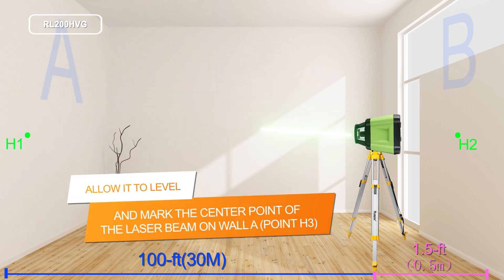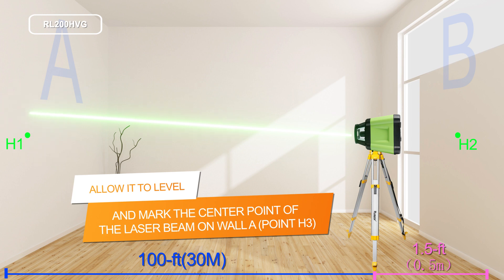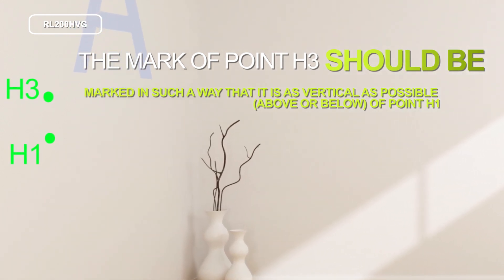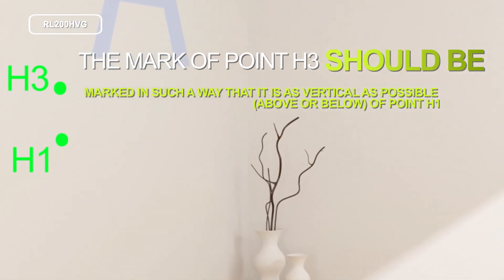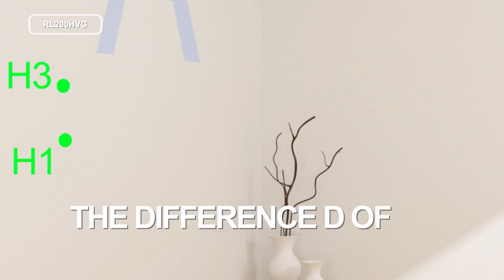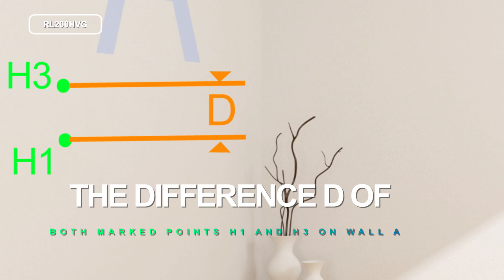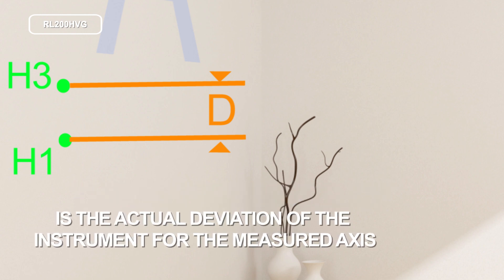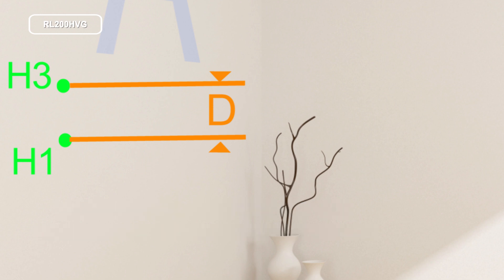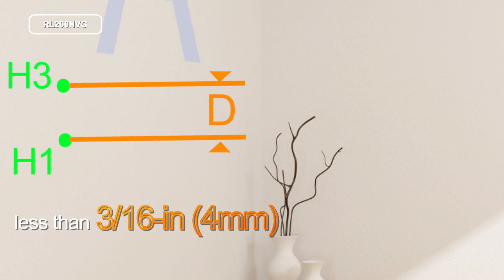Allow it to level and mark the center point of the laser beam on wall A. The mark of point H3 should be marked in such a way that it is as vertical as possible above or below point H1. The difference D of both marked points H1 and H3 on wall A is the actual deviation of the instrument for the measured axis. The value of D deviation should be less than 3/16 inches or 4 millimeters.